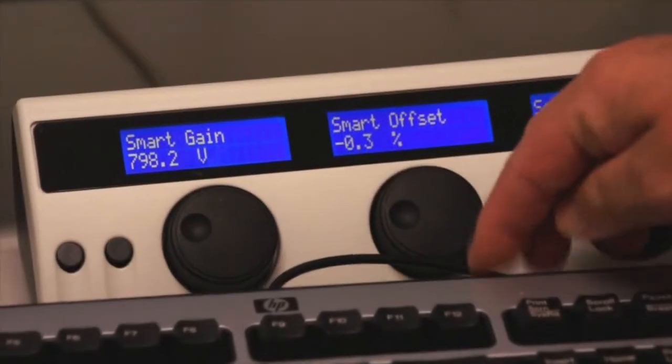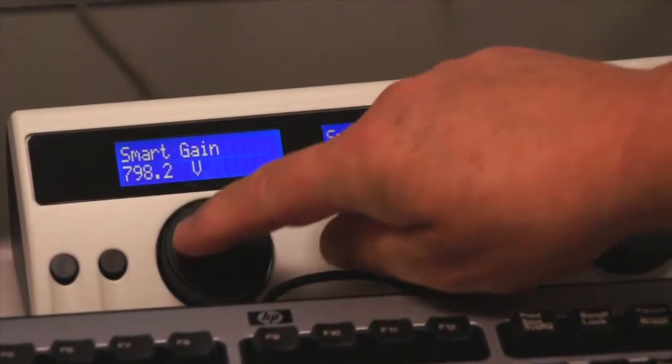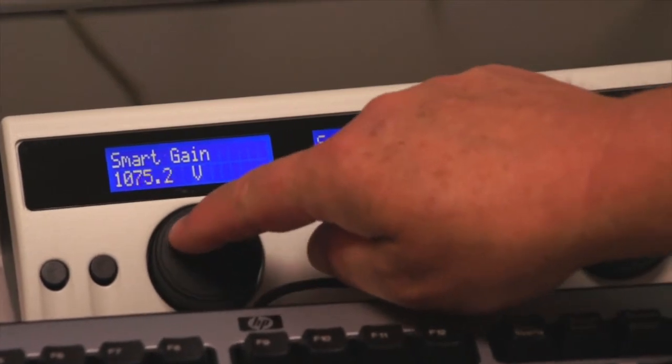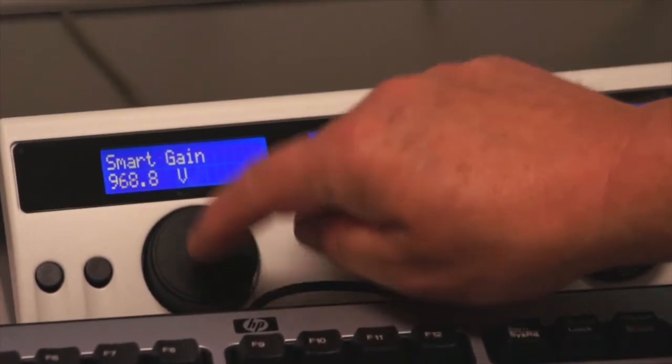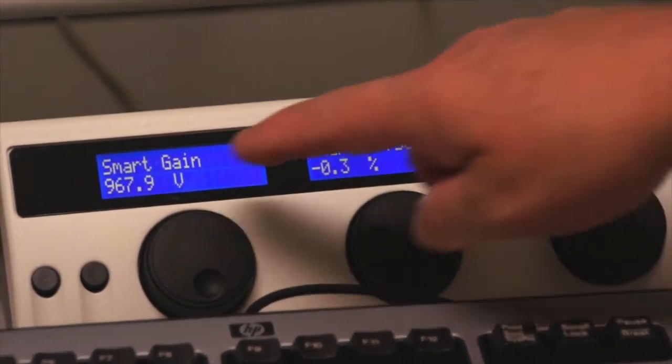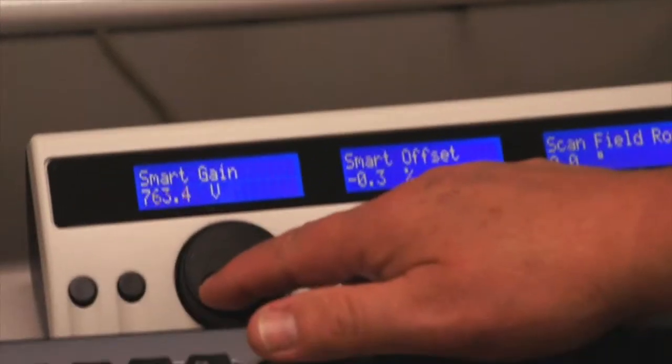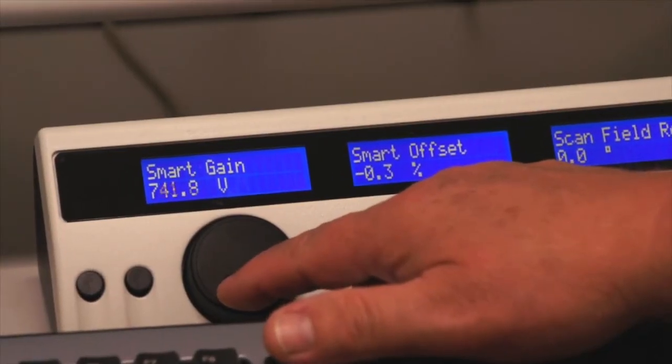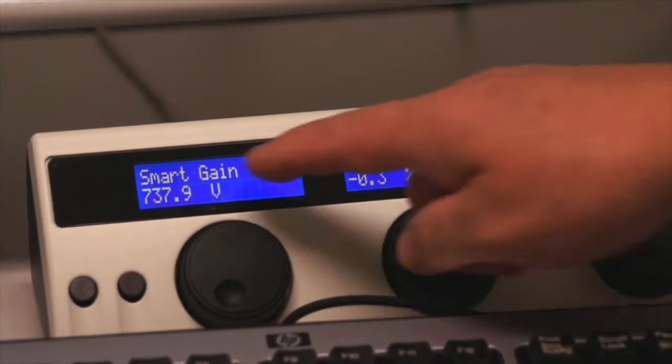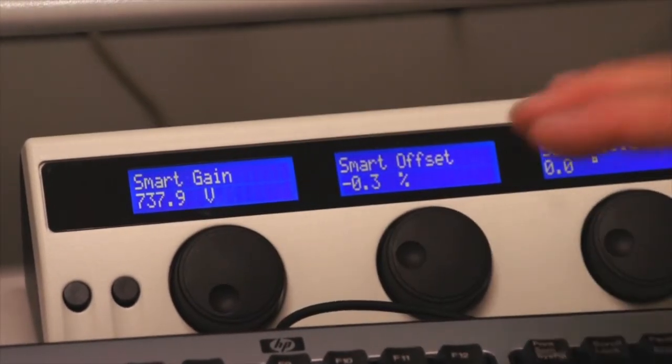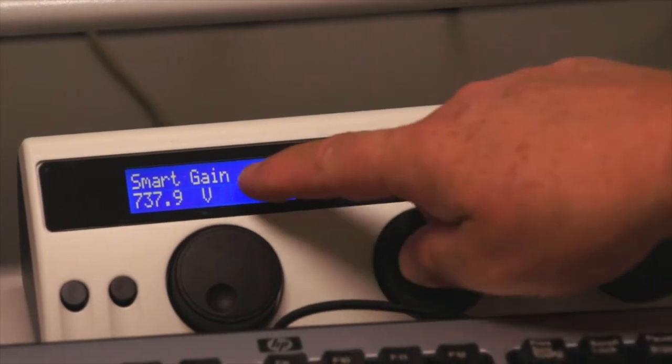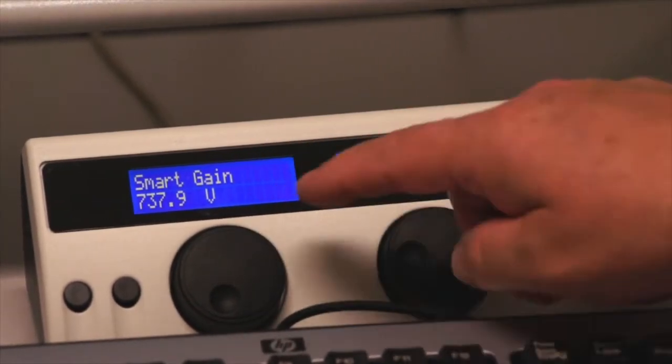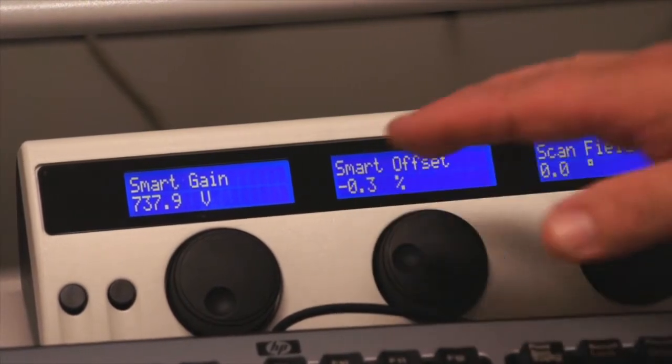And I select my gain and my offset. It's kind of like contrast and brightness by using these two knobs on the smart bar. And so I want to increase my gain until I have a few blue pixels at around 900 or 950. As you can see here, I have quite a few blue pixels. So I'm going to lower my smart gain down until I see only a few blue pixels. Now that's pretty low, which tells me that my laser could probably come down even a little bit more. A rule of thumb is to have the smart gain at around 900 to 950 volts.